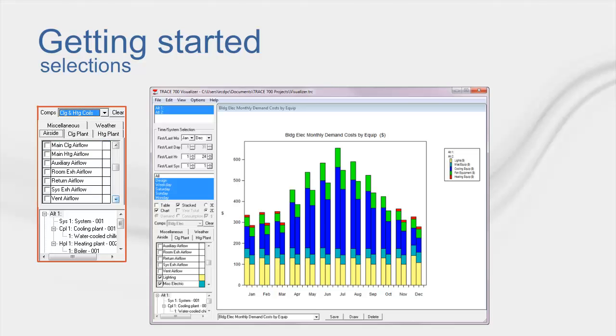We also have things like air flows for heating, cooling, exhaust, ventilation, and others. This is incredibly important for things like demand control ventilation. Since no report shows the air flows for every hour, there's no other way to tell if your DCV is working. But with this, you can view the ventilation rates for every hour and confirm that the ventilation airflow is fluctuating as it should.